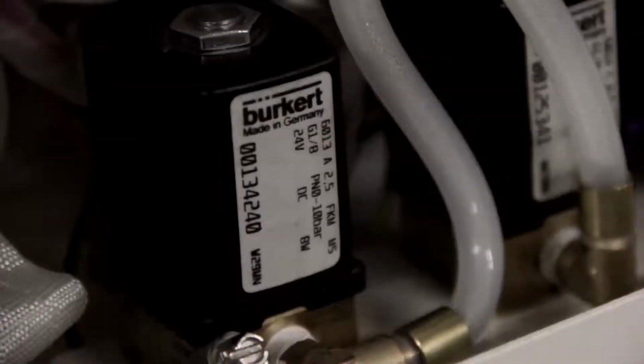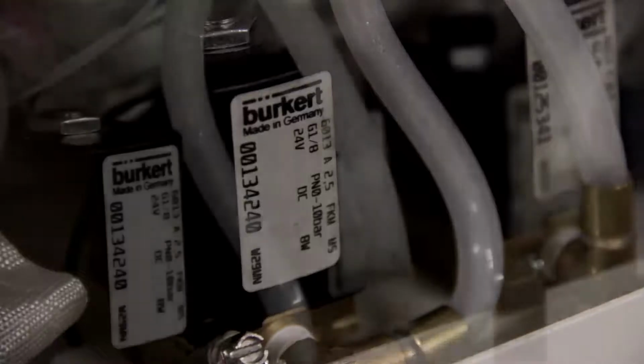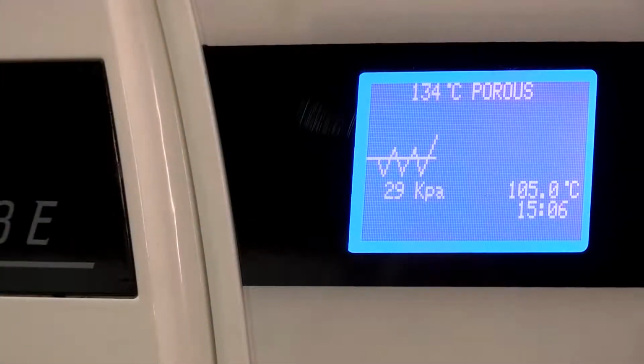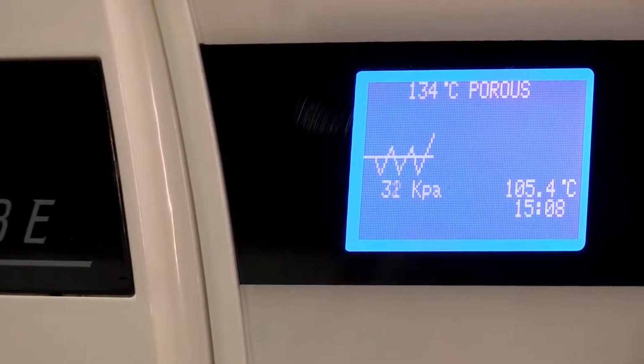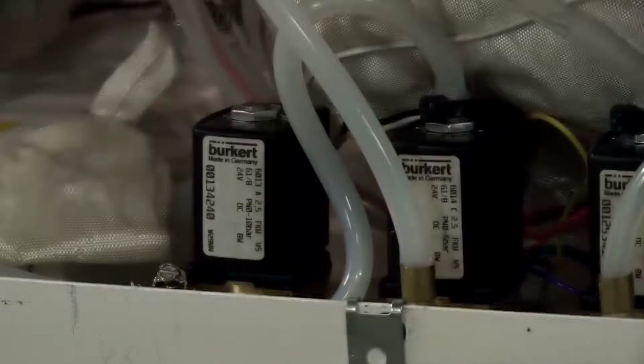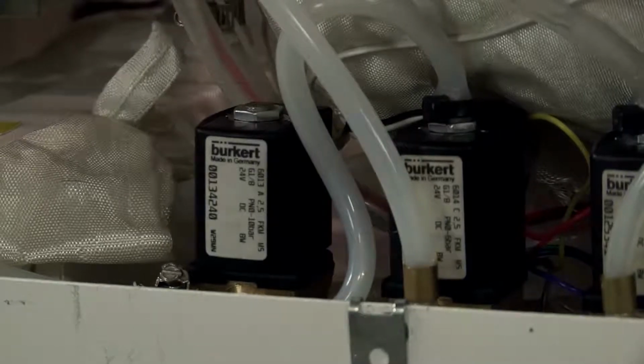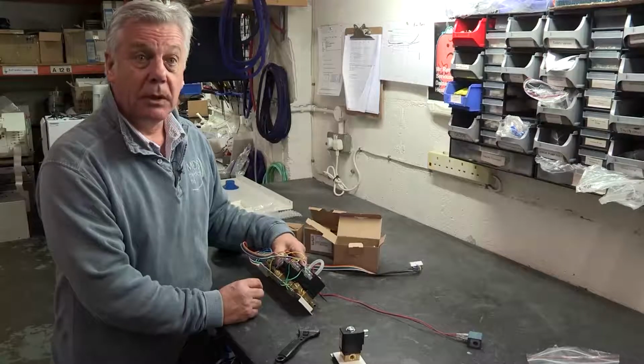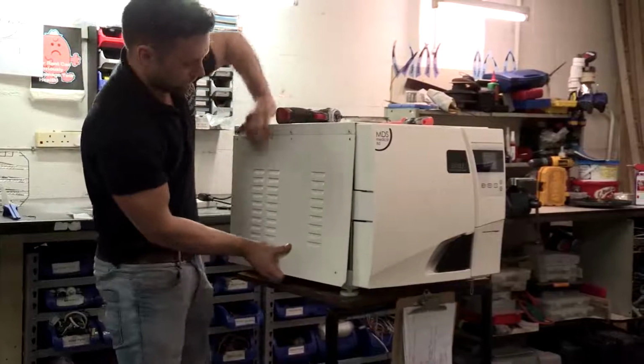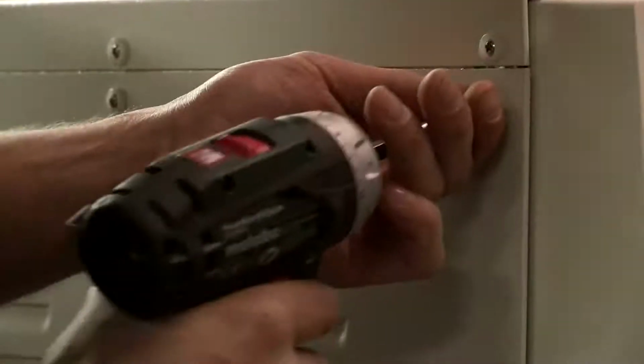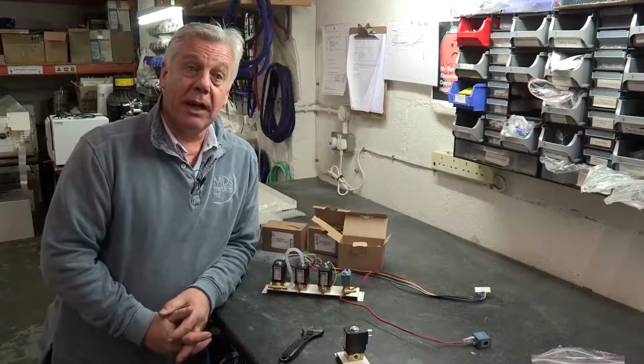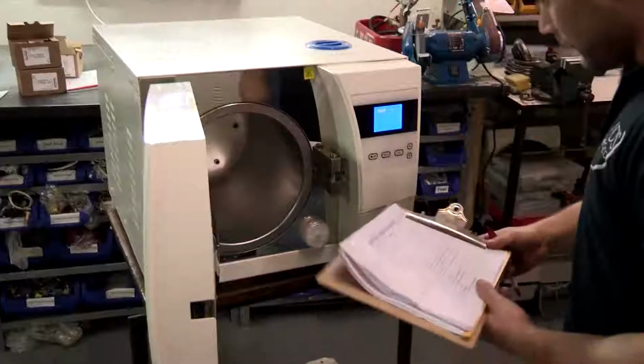So what we decided to do, we would put in the Burkert valves and the German vacuum pumps. The engineering of this valve is superb. As far as I'm concerned, it is the Rolls Royce of valves. Depending on the duty, we say to the dentist, every 6 months, we should be servicing your machine. But what we're finding with this particular valve is we most probably could go for 2 years without even changing anything on that valve, or even more.